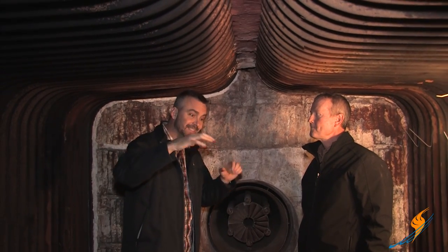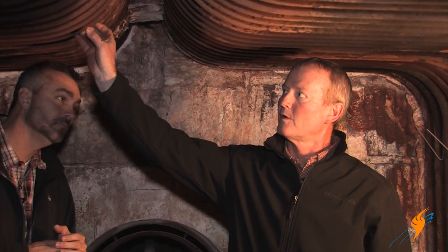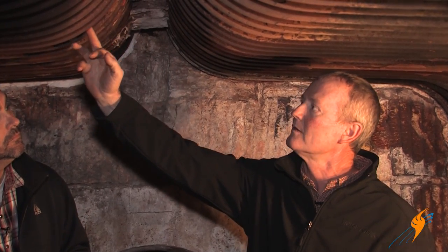Let's talk about what we mean by seal — when you're looking at the walls and the tubes inside the furnace, everything is sealed tight. This technology came out about 30 years ago and everybody has gone to it because of emissions. The old technology just had these tubes butted against one another, so you always had gaps, and you would create CO because you'd short-circuit between here and the stack — unburnt gases going out the stack creating CO. To make the boiler more efficient and keep emissions down, they now seal-weld ligaments to the tube itself, and at the factory we seal-weld these ligaments together, so it's a completely sealed furnace with no chance of combustion gases short-circuiting out the stack. Six rows of tubes — one inside that's sealed, one outside that's sealed, and then four intermediate where the gases turn and go back to get the heat transfer we're looking for.